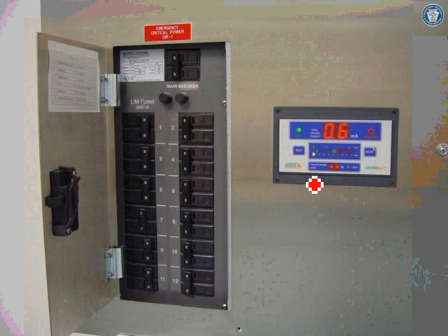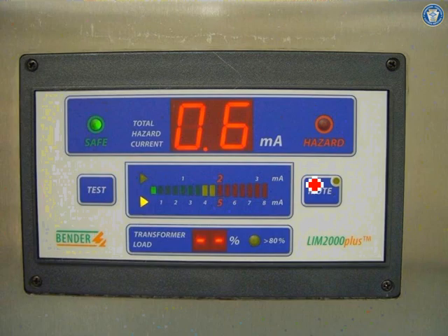When you run an ungrounded system, you're supposed to monitor the ground current that goes to the ground, which is typically what they use in the hospital. So you're monitoring the total hazard current that's going, and it could trip or alarm. You are to monitor the ground faults on an ungrounded system, and if it reaches a certain value, you are supposed to act, because if you allow a ground fault to sit in an ungrounded system, it will escalate into a fire. It will arc into a fire. So you're supposed to measure it.